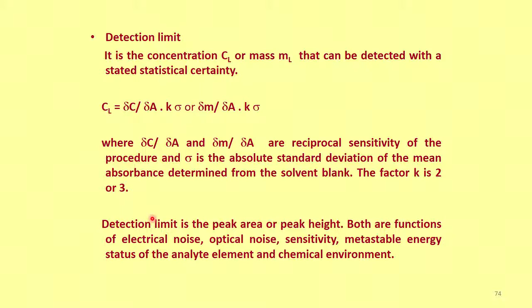Okay. So, detection limit is delta C by delta A into k dot sigma, or delta m by delta A into k dot sigma, where k is the factor, k is 2 or 3, and sigma is the absolute standard deviation. So, the detection limit, what I have shown you earlier in the table are these numbers. Okay. So, the detection limit can be measured either using peak area or peak height, that is the emission line spectrum. Both are functions of electrical noise, optical noise, sensitivity, metastable energy status of the analyte element and the chemical element environment, that means that is matrix matching. So, the detection limit can vary for different systems.